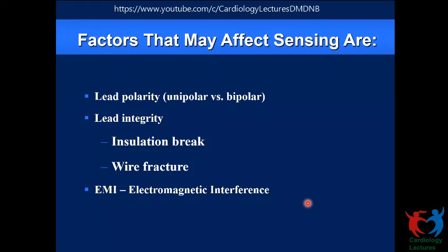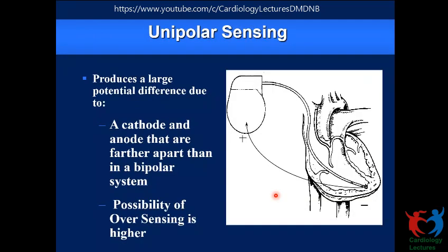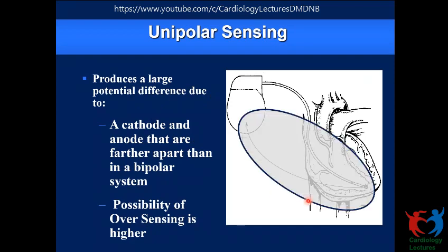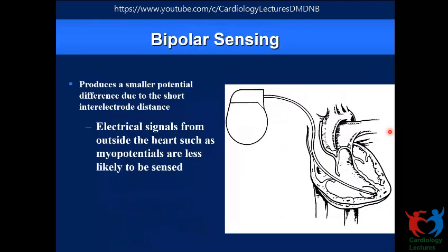Electromagnetic interference: the conventional electricity that we deal with has a 50-60 hertz frequency, which is the same as the peak frequency of the R wave as well. So we cannot filter it out adequately, and it will interfere with the pacemaker if the patient comes into contact with that. Polarity, as we said, can interfere with sensing, because a unipolar system senses between the tip and the can. So this can pick up myopotentials and get oversensed. And if there is electromagnetic interference, the body tissues act as a large antenna. It can easily pick up the electromagnetic interference, even if it is a little far away. So unipolar pacing systems are inherently more susceptible to oversensing, unlike a bipolar, where the entire sensing is between the tip and the ring electrode, which is less susceptible to oversensing.